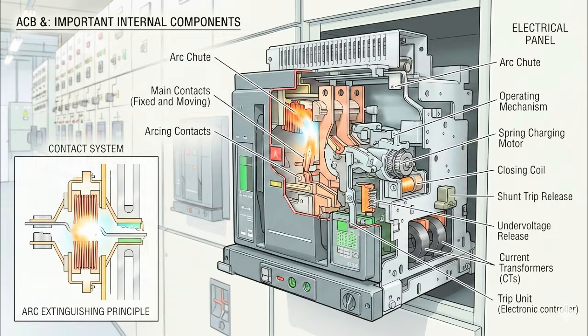The third one is the trip unit. The trip unit is the brain of the ACB. It detects overload, short circuit, and earth fault conditions and triggers the breaker to trip automatically. The fourth one is the closing and tripping mechanism. This mechanism controls the on and off operation of the breaker, either manually or automatically.